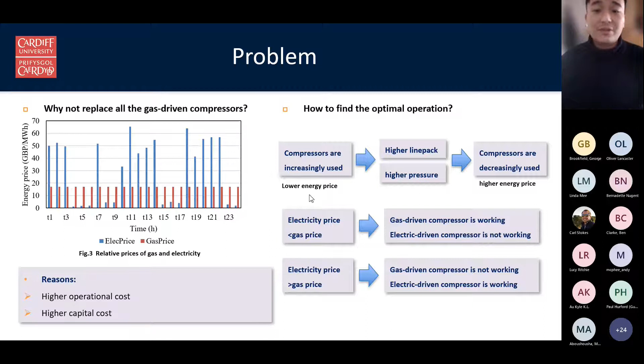This is the simplified control system of the hybrid compressor station. Two decisions are made by the system. The first is whether to turn on the compressor unit. If the compressor is not required, valve 1 opens while valves 2 and 3 close, so gas only flows through the bypass line, and the compressor is off. Otherwise, the compressor is used and valve 1 closes.